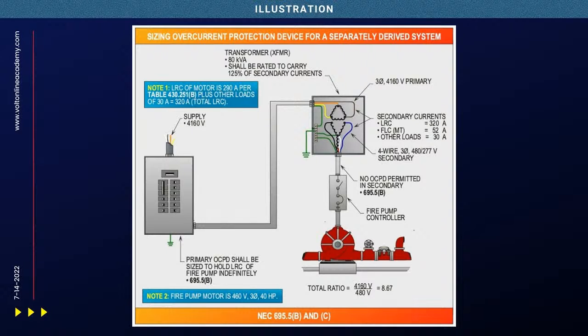Now, the primary that's coming over there is 4160 3-phase. And we've already done the work here for you, telling you what these secondary currents and everything are. On the secondary, it's a 480/277 volt secondary 3-phase. And you're going to see secondary currents there. We're going to tell you the locked rotor current is 320 amps. I'll explain all this in just a second. Okay. Then we're going to tell you the full load current of the motor is 52 amps. And then there are other loads being supplied here also that are rated at 30 amps. So we've already made all this up.